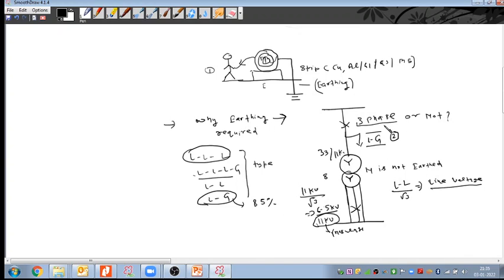So the system is designed for the L-G fault because its probability is higher. And for a three-phase fault, earthing and grounding will not have any impact. Basically, whenever there is an unbalance, a neutral shift will occur, and that will make the neutral potential non-zero. And that is why earthing is a must. Yes, needed.